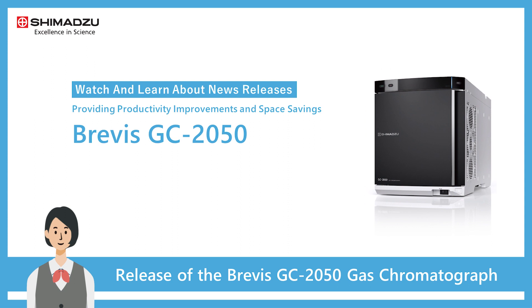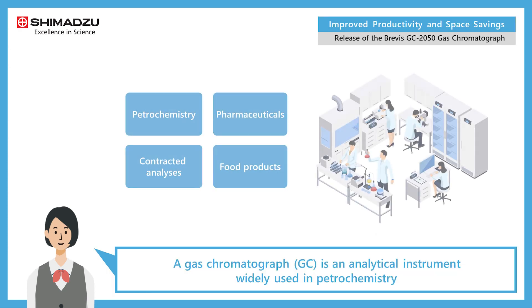Shimadzu Corporation will release the Brevis GC 2050 gas chromatograph. This instrument provides both productivity improvements and space savings while maintaining a high level of basic functionality and expandability of optional products, while inheriting the basic functionality of the Nexis GC-2030, our top-of-the-line model released in 2017. This model is approximately 35 percent narrower.